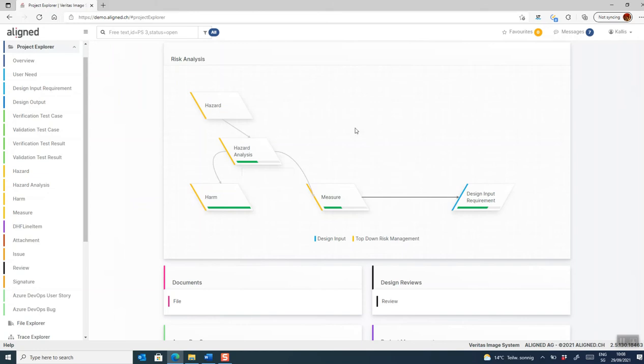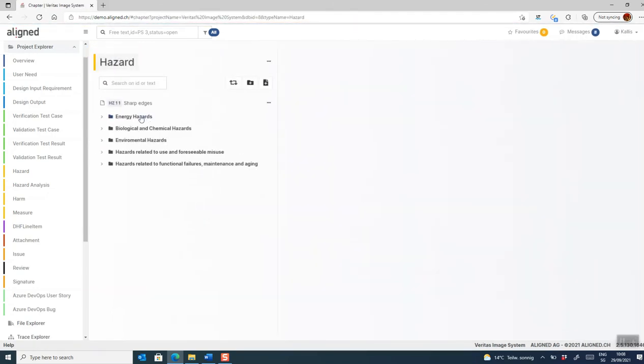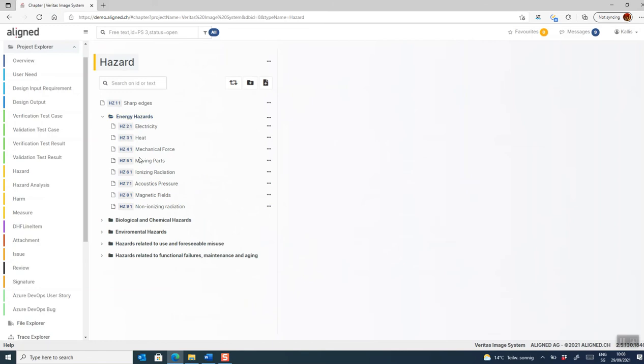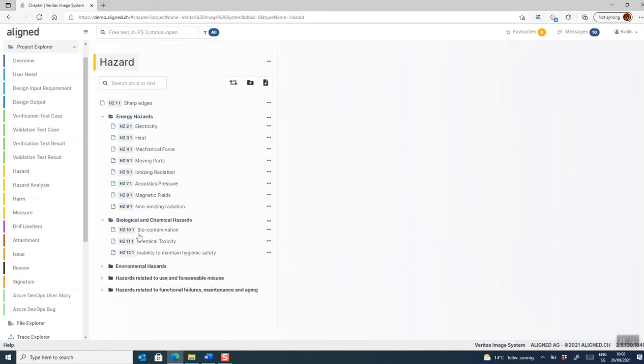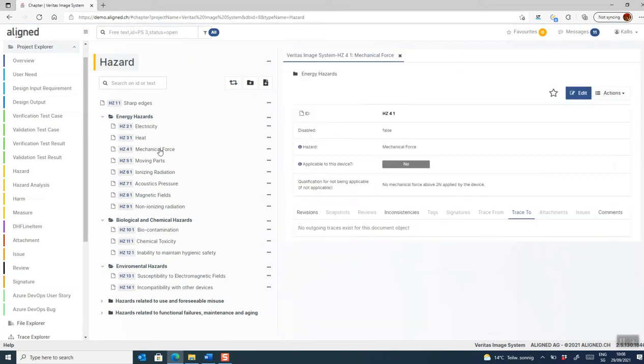I'll start out by showing how you can perform risk identification. In this case, we're going to use a generic list of hazards. This is something that is often used in medical device risk assessments. And the idea here is that for each individual potential hazard, you can then decide whether this generic hazard is applicable to your device.